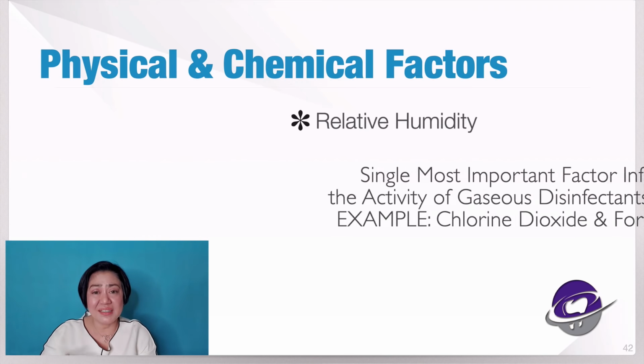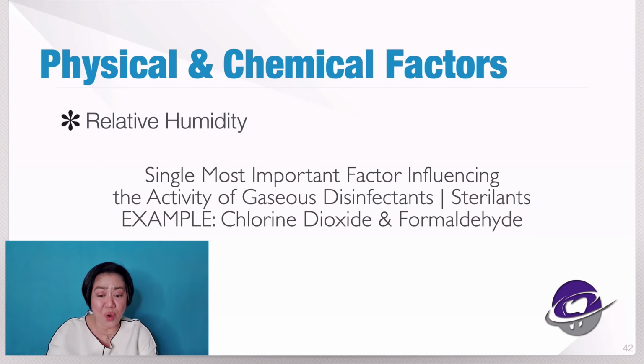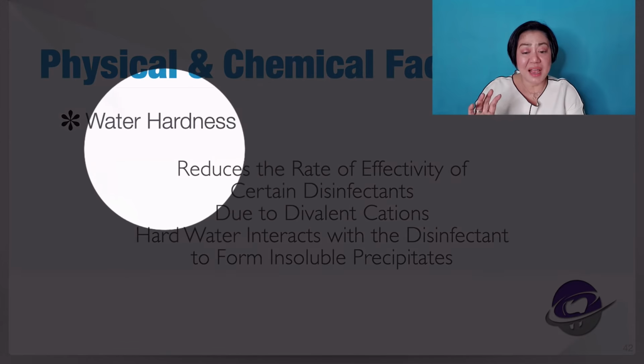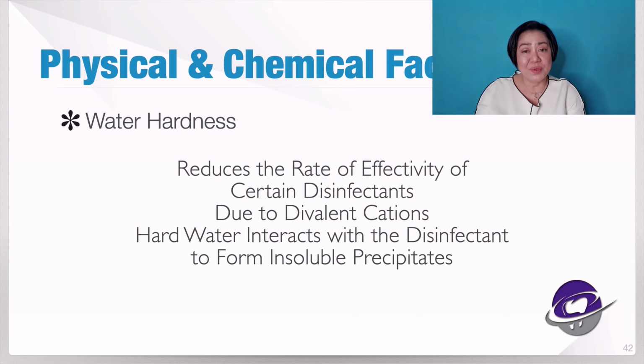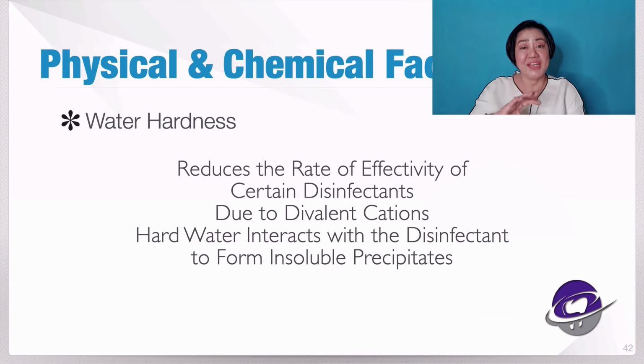There are materials that get damaged when the level of humidity is high, or if the humidity is too low. So it gets affected by that, for example, gaseous disinfectants. So we have to be aware of these things, especially when we are trying to store disinfectant solutions or even equipment. And another thing, water hardness. Now, this has something to do with how we clean our instruments, or what type of water we use when we're trying to sterilize. The best example is the autoclave.